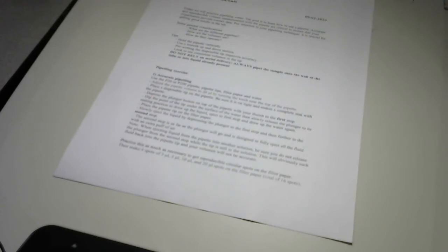Alright, and this one, the biggest one, is 100 to 1000. So 100 microliters is the minimum, 1000 is the maximum that this can take. So you see, now in this one, the top one became red. That means you don't have to worry about the 10. If it's 80, the top one is red. The bottom 2 are 8 and 0. How many microliters is it? 800? Yeah, 800, because the top one we're not seeing.